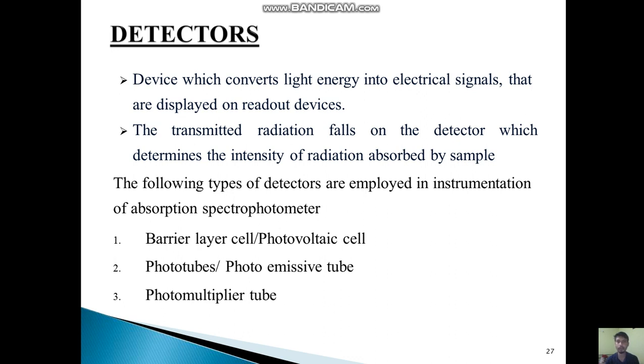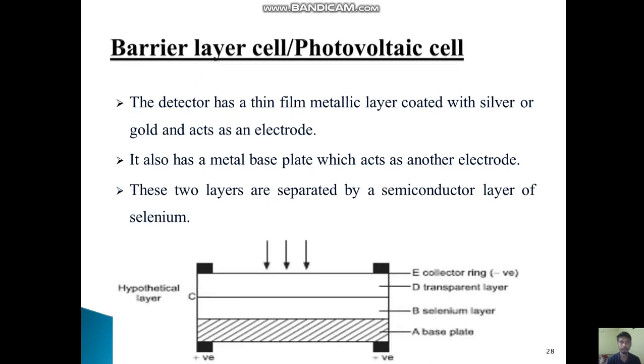The transmitted radiation falls on the detector which determines the intensity of radiation absorbed by the sample. Some detectors are the barrier layer cell or photovoltaic cell, photo tubes or photo emissive tubes, and photo multiplier tubes.